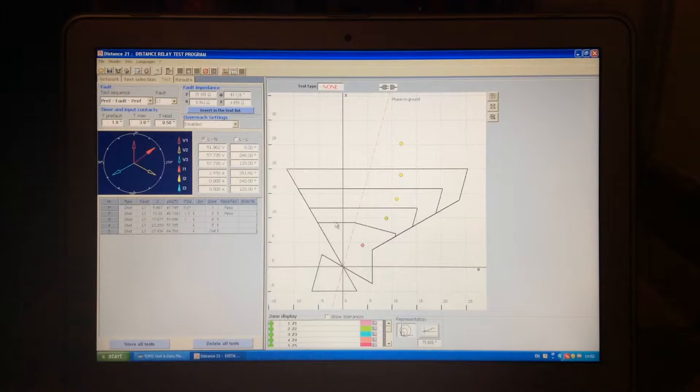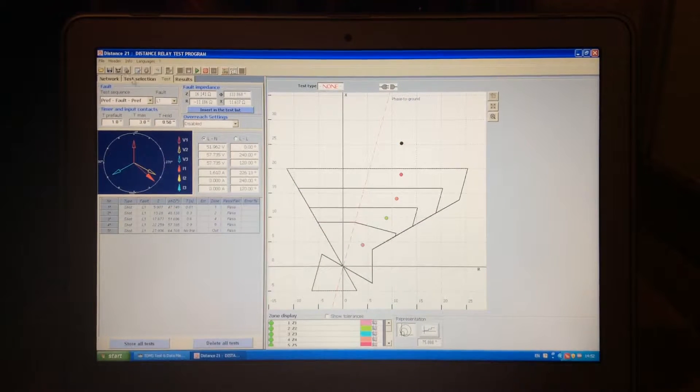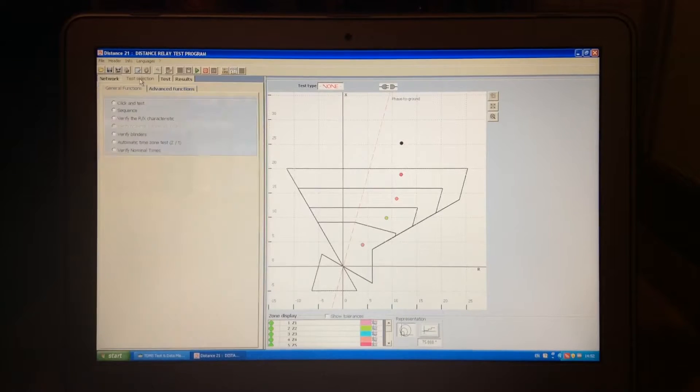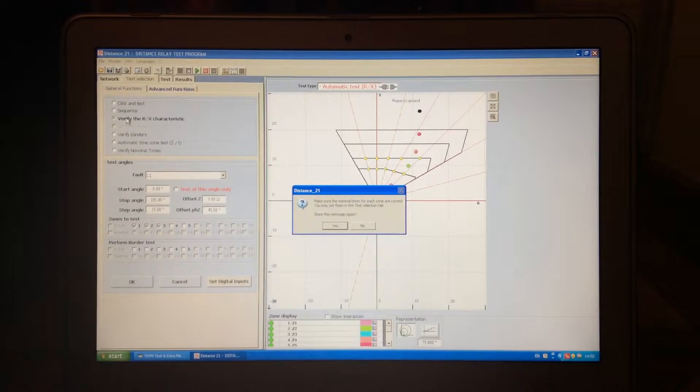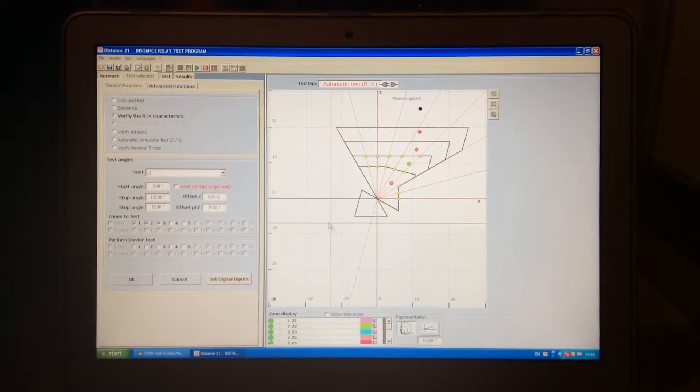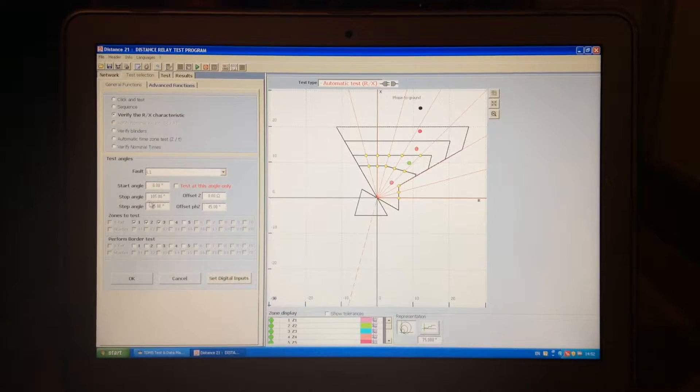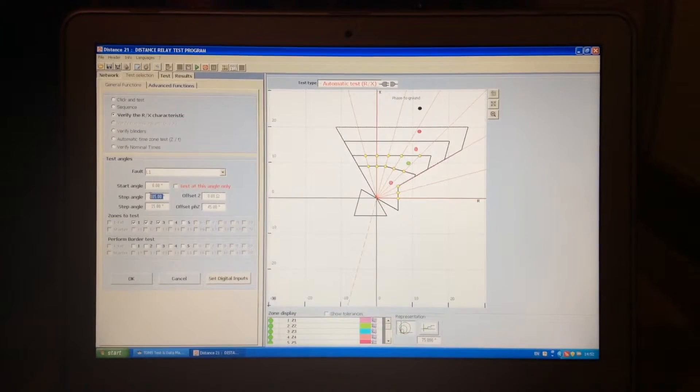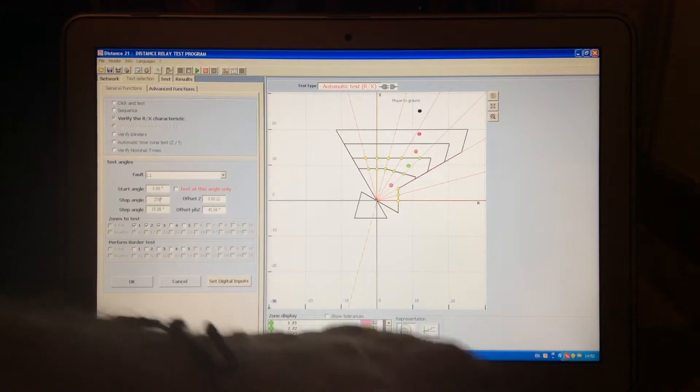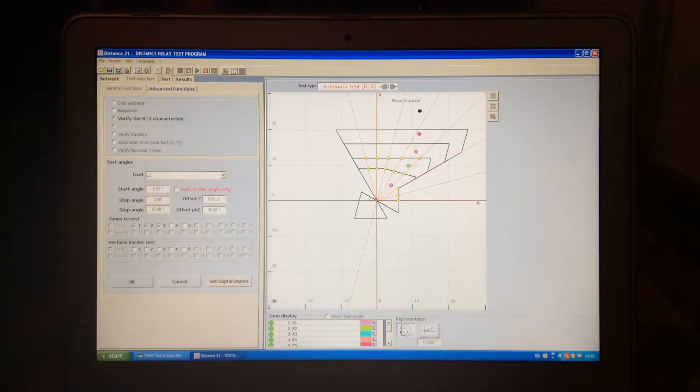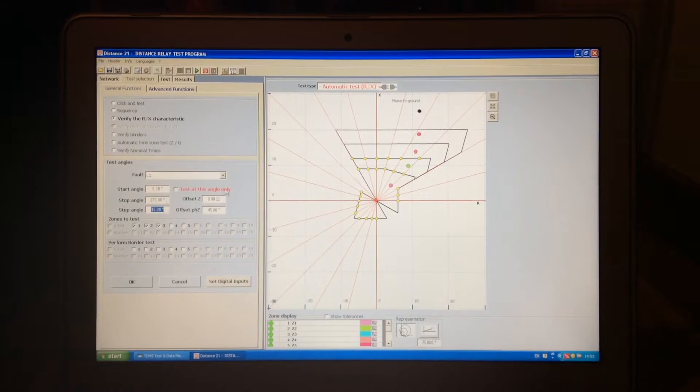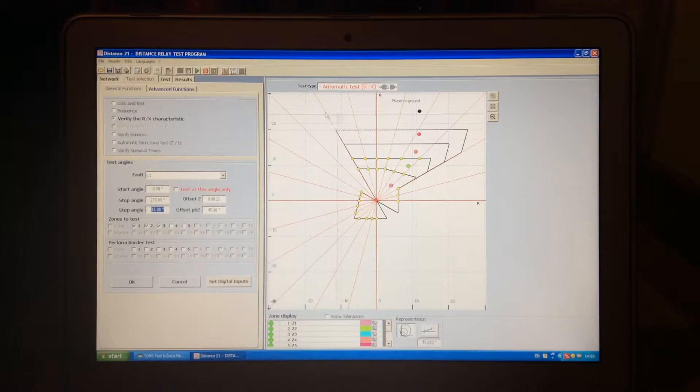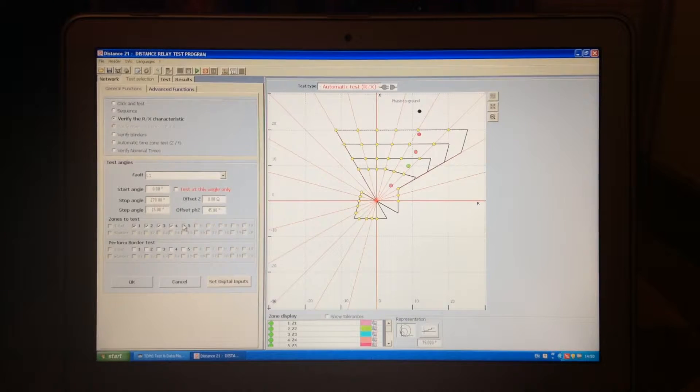So yes, we will simulate, and now we get all the results. After the sequence, we have the verification of RX characteristic, where you can set up the starting angle, stopping angle. Let's say that it will be 270, and with the step angle of 15 degrees, you can here test the whole characteristic, and you can decide which zones would you like to test.